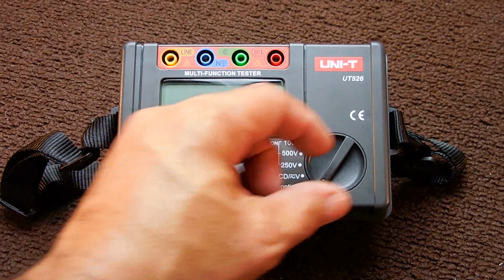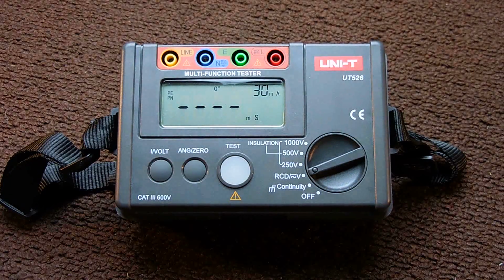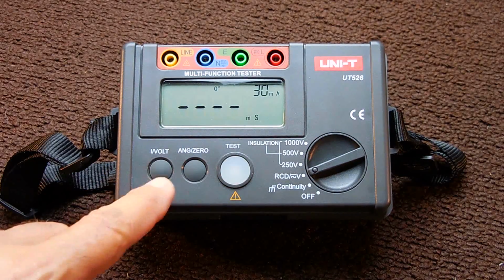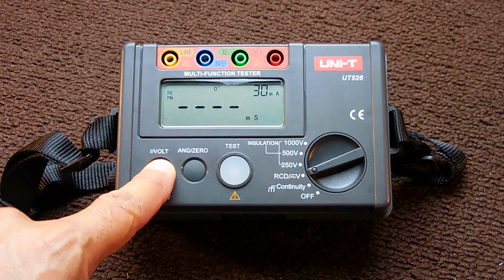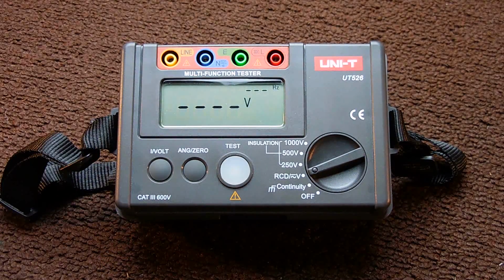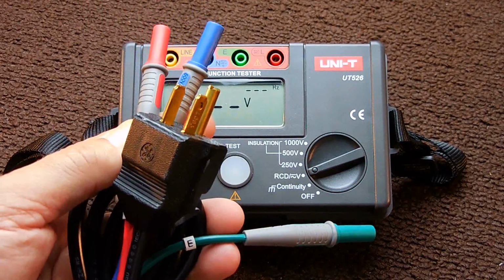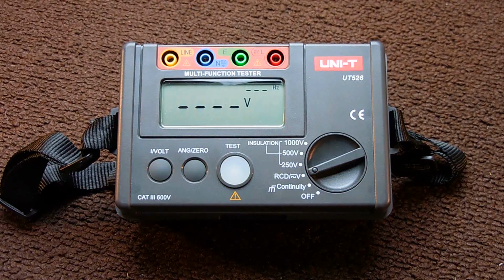So you're going to put this to RCD V. This right here is trip current. This is another setting that I usually don't use. So you push and hold this button. Take the connector, and you plug it into a receptacle, just like you see right here in this clip. Plug this into the receptacle.